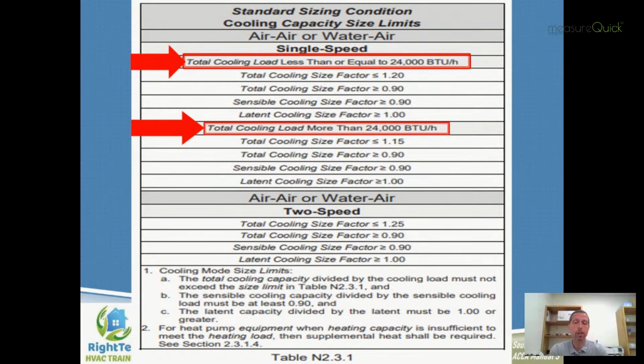And so there was a lot of loads, especially in modern construction, where, to be quite frank with you, the systems that were available really wouldn't match up and fall within that 15% parameter for a lower load type of home like this. So we recognize that concern there, and this is something that a number of people from industry brought to light as the new Manual S was coming about. So the 15% oversizing for single stage equipment still remains for larger loads, 24,000 BTUH and above. But for smaller loads, we've given, again, an extra 5% buffer there to make sure that you can actually buy an OEM package system that will fit within the criteria.